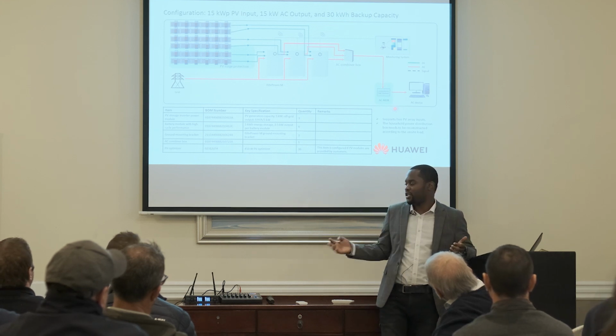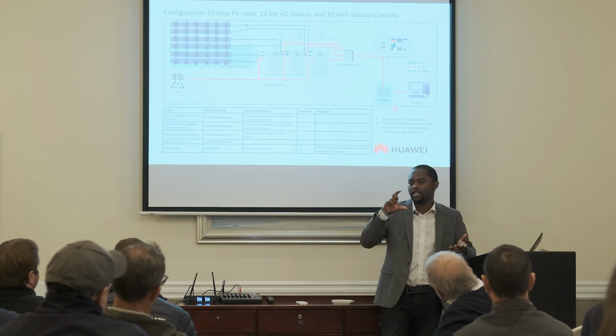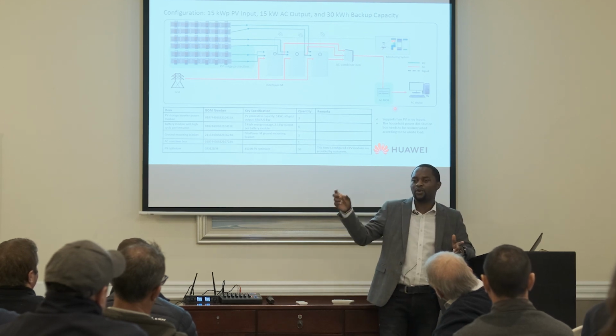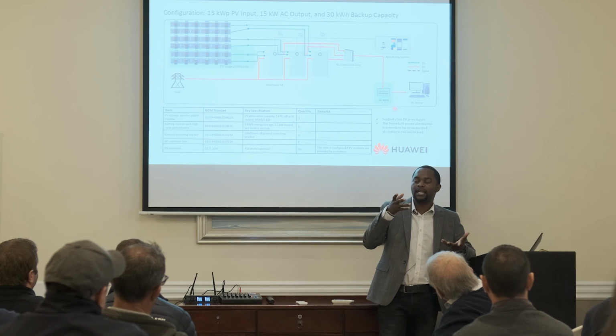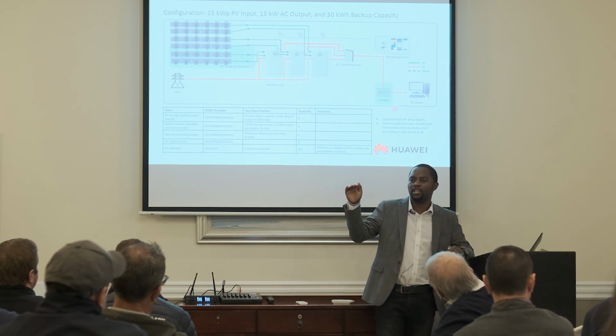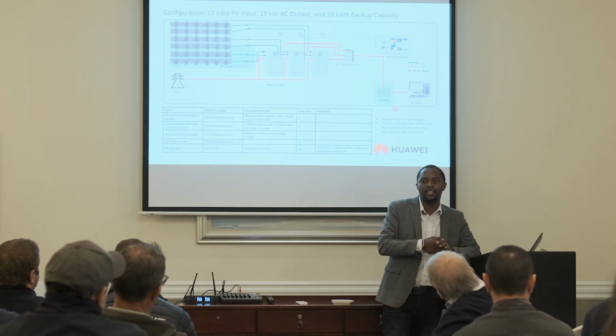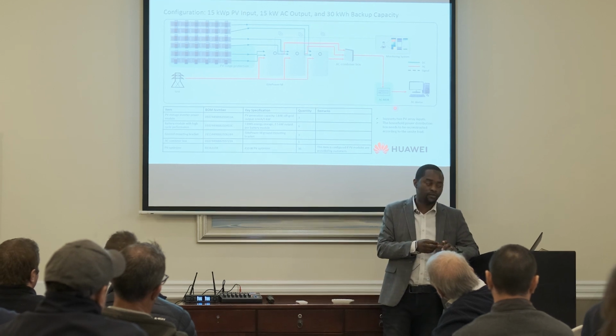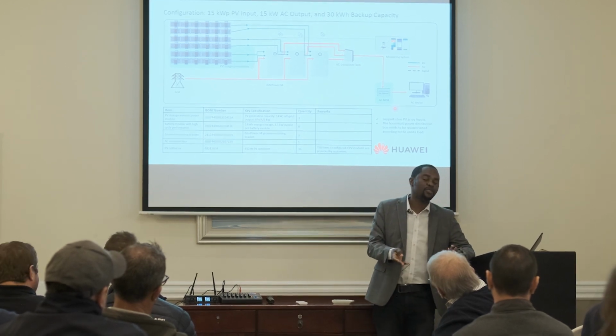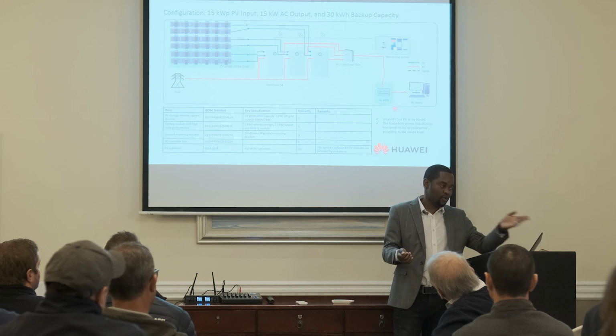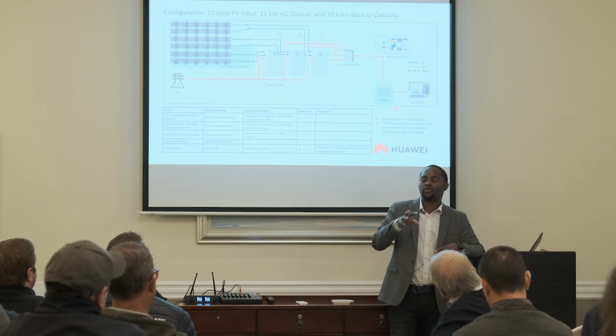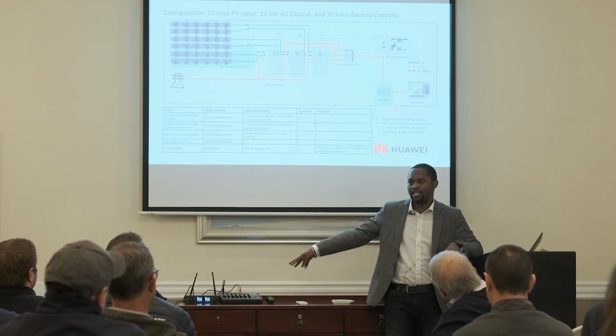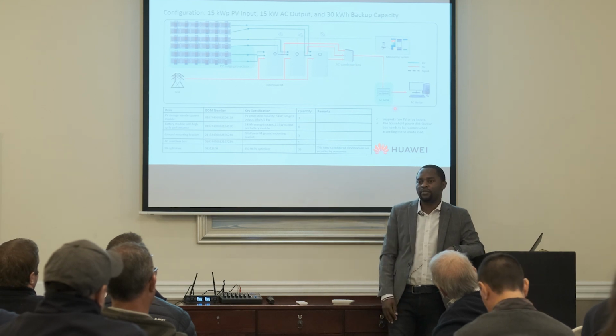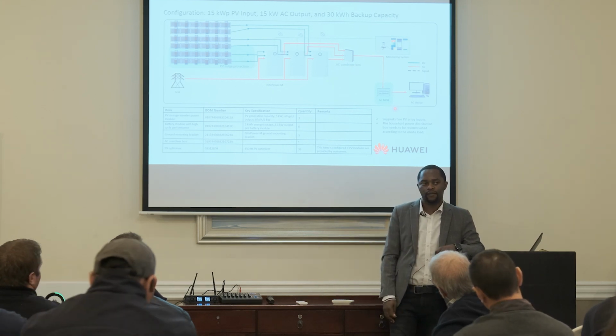Then the inverter can take that wider frequency range and it gives you 50 Hz on the dot, because it has got circuitry that is actually giving you a stable output. It's not riding on what you are giving it. So you realize that if you've got a 6 kVA generator that you are failing to use on your Sunsynk or even on the INVT for that matter, you can actually use that generator on the Huawei inverter. Yeah.